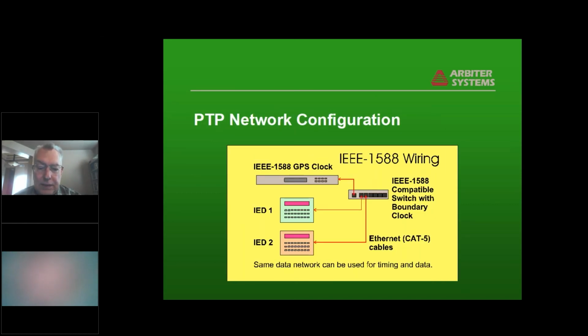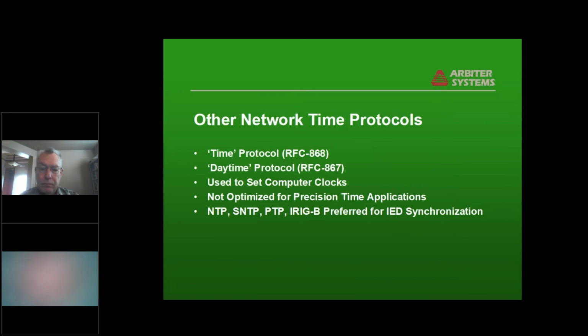PTP network is nice because the same data network is used for both timing and data. That's the whole reason for doing it. And the difference is you have to have an IEEE 1588 compatible GPS clock, an IEEE 1588 compatible IED, and an IEEE 1588 compatible switch, often with a boundary clock or even now a transparent clock. Other network time protocols exist. Time protocol, daytime protocol, they're both standardized by RFCs, used to set computer clocks, and they still are used for that, but they're not optimized for the kind of things we do in the power industry. So the power industry tends to use NTP, SNTP, PTP, and IRIG instead.